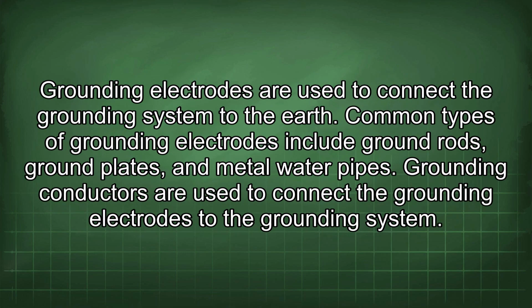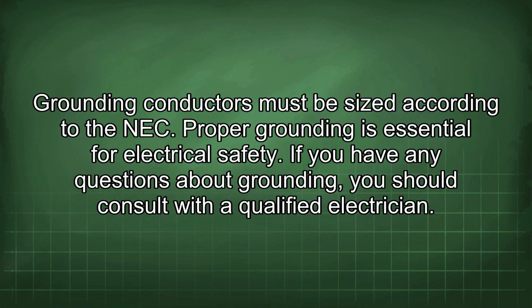Grounding electrodes are used to connect the grounding system to the earth. Common types of grounding electrodes include ground rods, ground plates, and metal water pipes. Grounding conductors are used to connect the grounding electrodes to the grounding system. Grounding conductors must be sized according to the NEC. Proper grounding is essential for electrical safety. If you have any questions about grounding, you should consult with a qualified electrician.